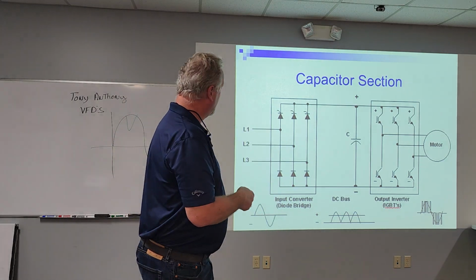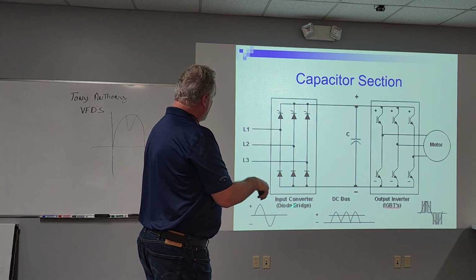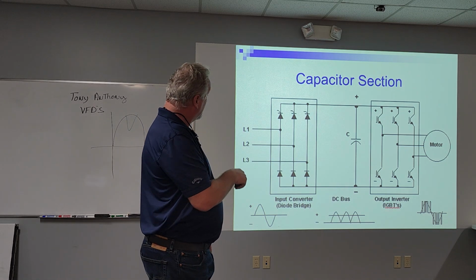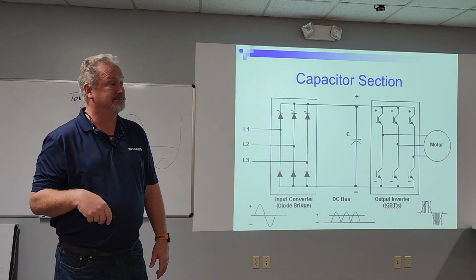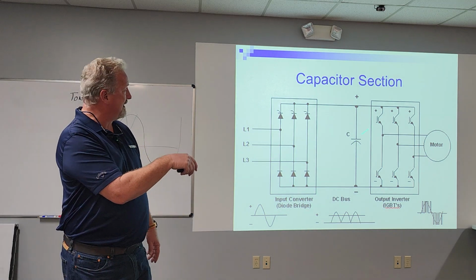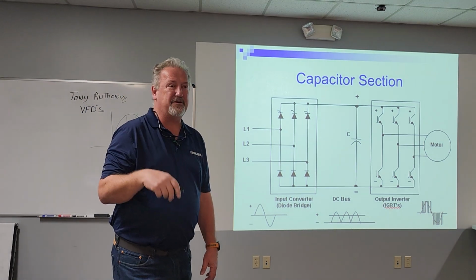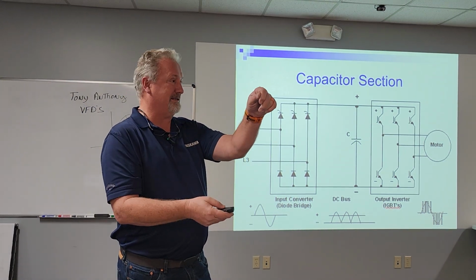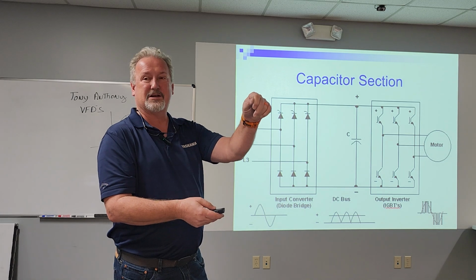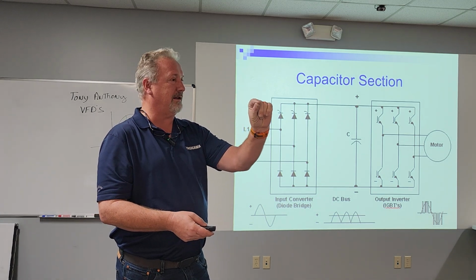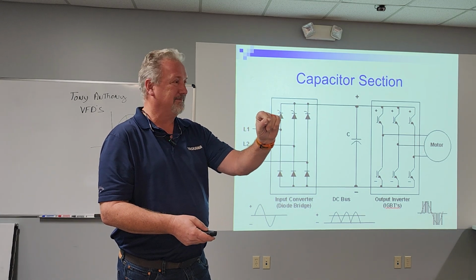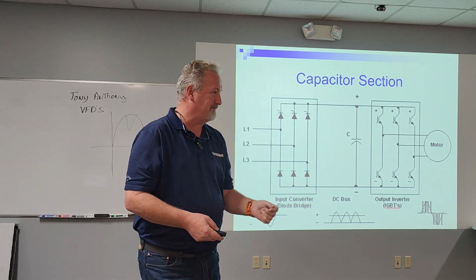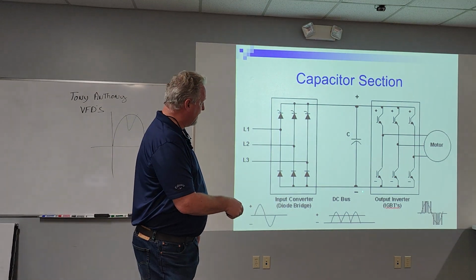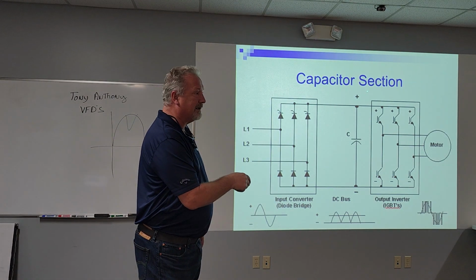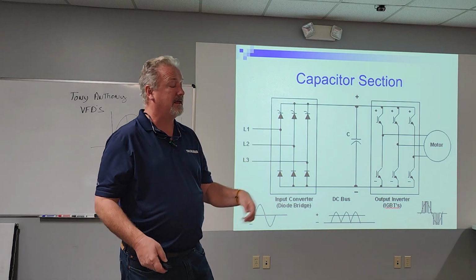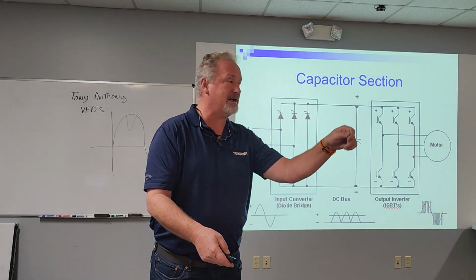To check the entire input, this diode bridge, you take your line leads off, make sure the drive discharges, make sure that capacitor discharges, give it a few minutes, then measure the DC bus. Don't trust that little red LED that we probably paid less than a penny apiece for. Measure the DC bus. Every drive will have a plus and a minus somewhere in the drive. That's your DC bus. Make sure your DC bus is de-energized.